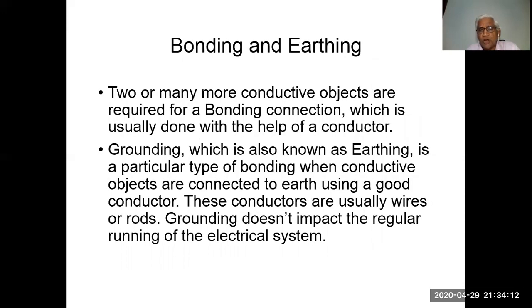Two or more conductive objects are required for a bonding connection, which is usually done with the help of a conductor. Grounding, which is also known as earthing, is a particular type of bonding when conductive objects are connected to earth using a good conductor. These conductors are usually wires or rods.